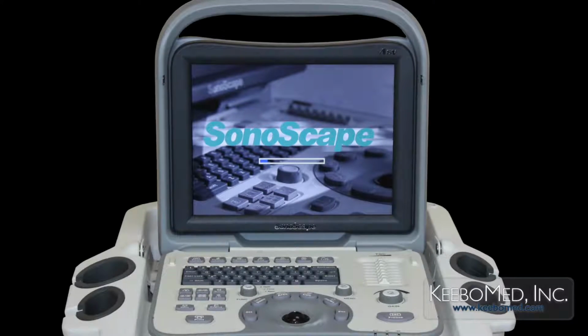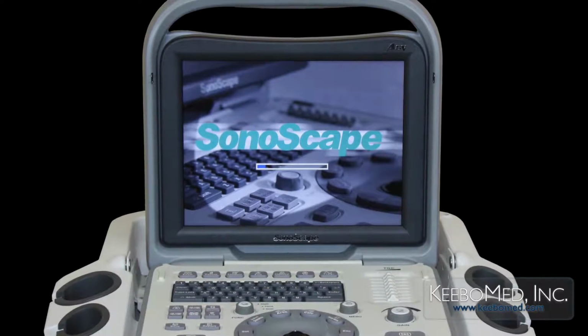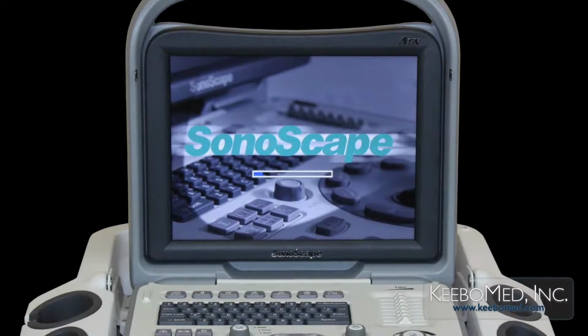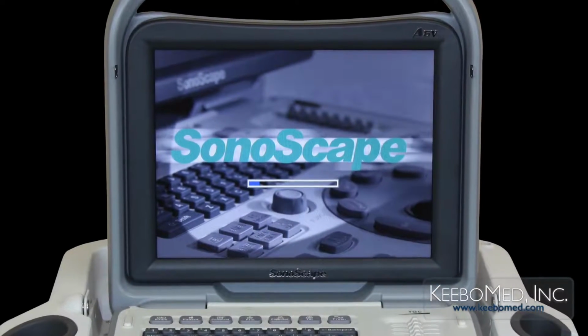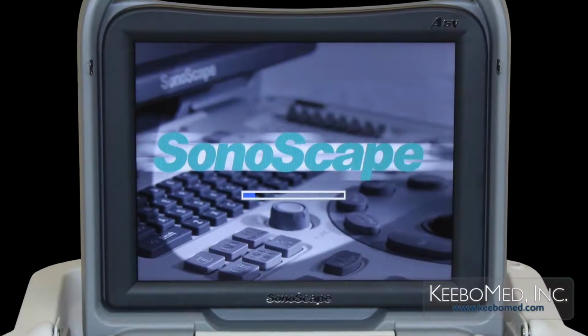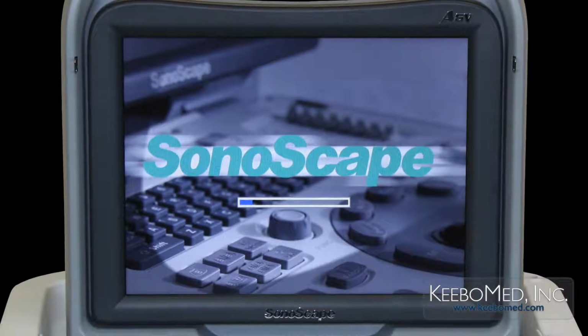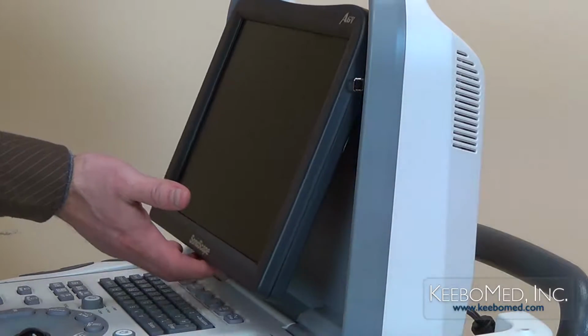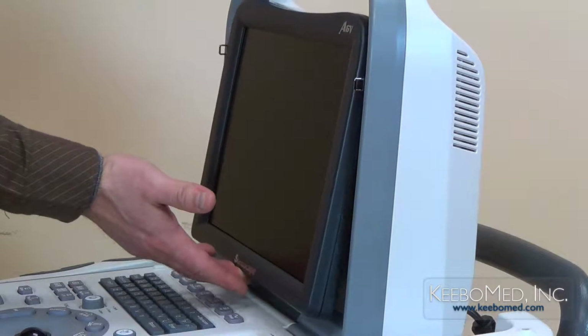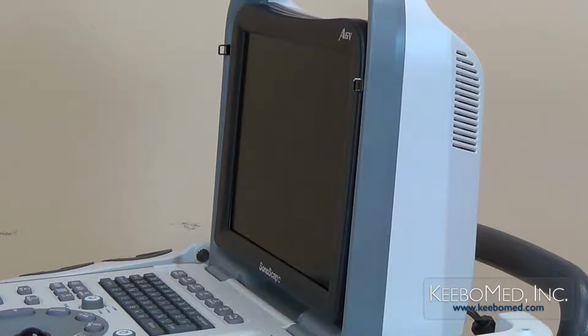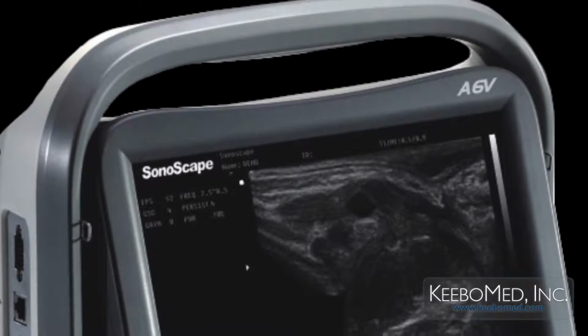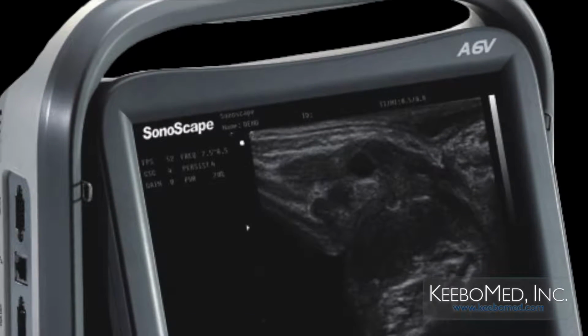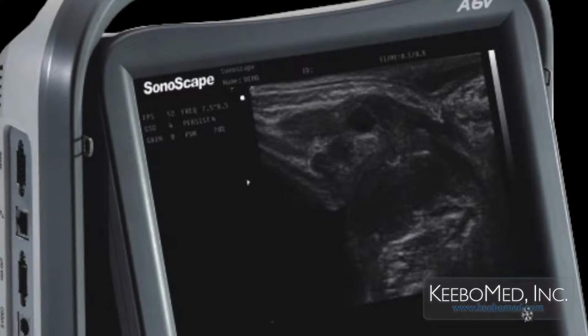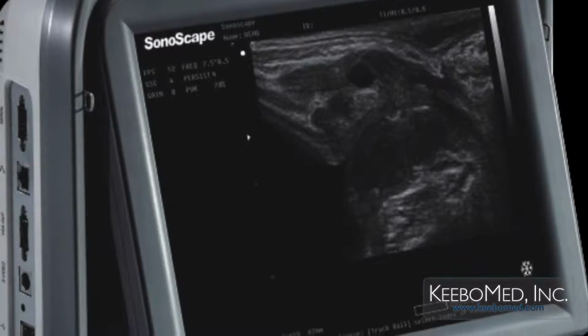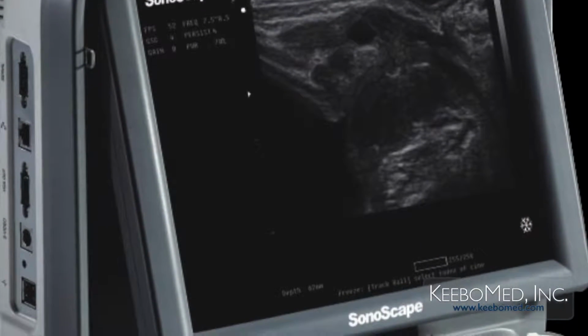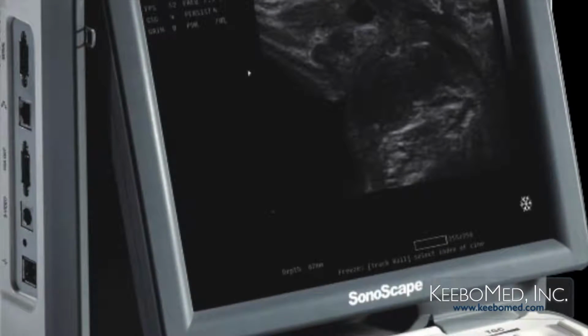The A6V has a large 12-inch adjustable LCD screen. The LCD screen is much better than a CRT screen found in many other ultrasounds. It will produce a better image quality, and it is also lighter in weight. The angle is also adjustable from 0 to 30 degrees, allowing for a better view of the screen. Images are displayed on most of the screen, making it very easy to work with. There are ultrasounds with 12-inch screens, but the image is only displayed on half of the screen, which will produce an image similar to only having a 10-inch screen.